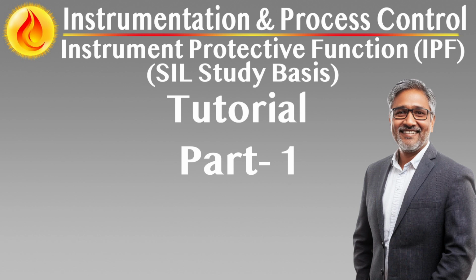Workflow for SIL determination. The methodology typically follows this sequence. Hazard identification. Process hazards are identified using structured techniques such as HAZOP or what-if analysis, generating a list of credible initiating events and potential consequences. Risk assessment. For each hazard, the severity and frequency are estimated. Factors include toxic release, fire explosion potential, equipment damage, and personnel safety implications.